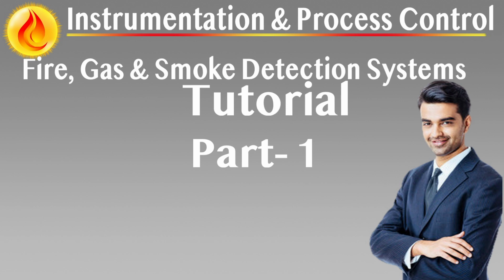Conclusion: open path gas detectors offer expansive area coverage, early plume detection, and robust fault diagnostics, making them an essential component in any modern FGS architecture. When sited and maintained correctly, they outperform clusters of point detectors in open, ventilated environments, especially where early detection of gas migration is critical. Their deployment, however, demands thoughtful alignment, threshold tuning, and environmental compatibility to ensure lasting system integrity and reliable detection performance.